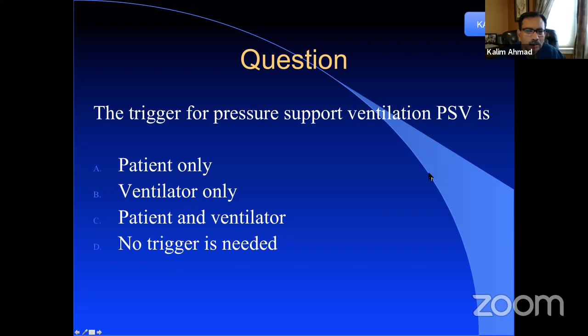So if the patient is not going to initiate a breath, the machine is not going to provide any breath to the patient. That's the reason, when Shabana talks about different alarms, we'll see how we safeguard this mode of ventilation in patients where we are concerned that the patient is not going to initiate the breath. So again, pressure support ventilation is primarily a patient-driven process. The ventilator plays only a supportive role, depending upon the pressure setting we put in, so that the flow goes into the lung. When it reaches the preset pressure, the patient takes over and decides how to exhale on the basis of the flow. Next slide.